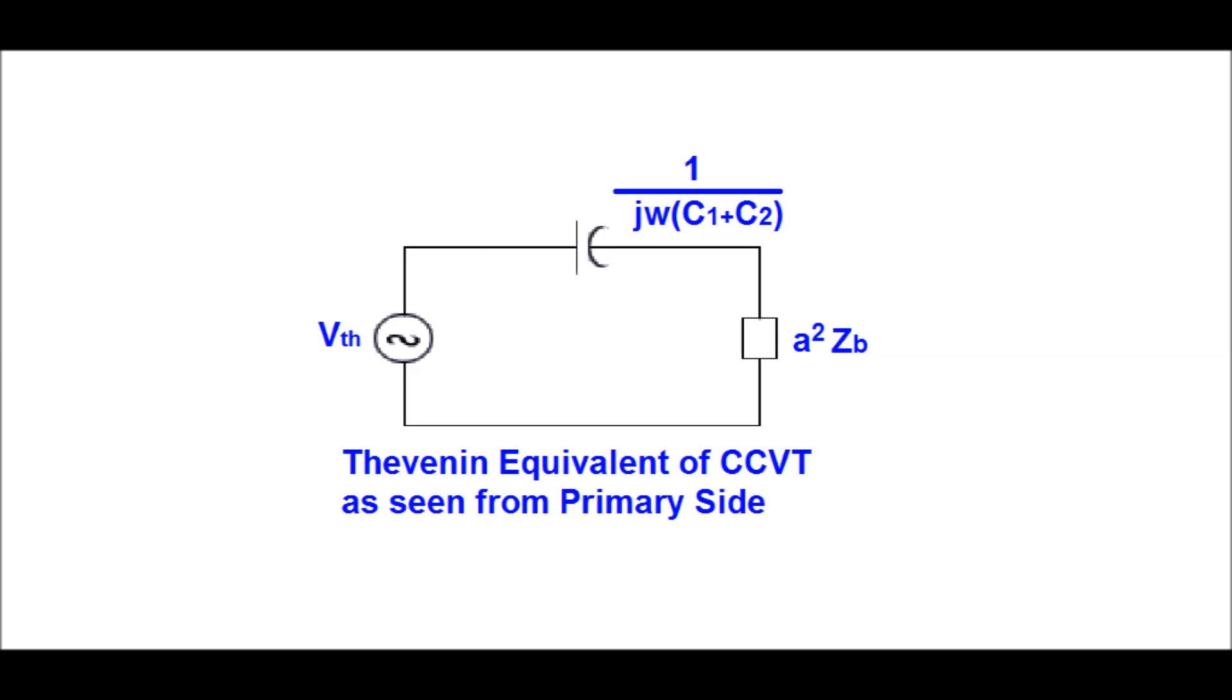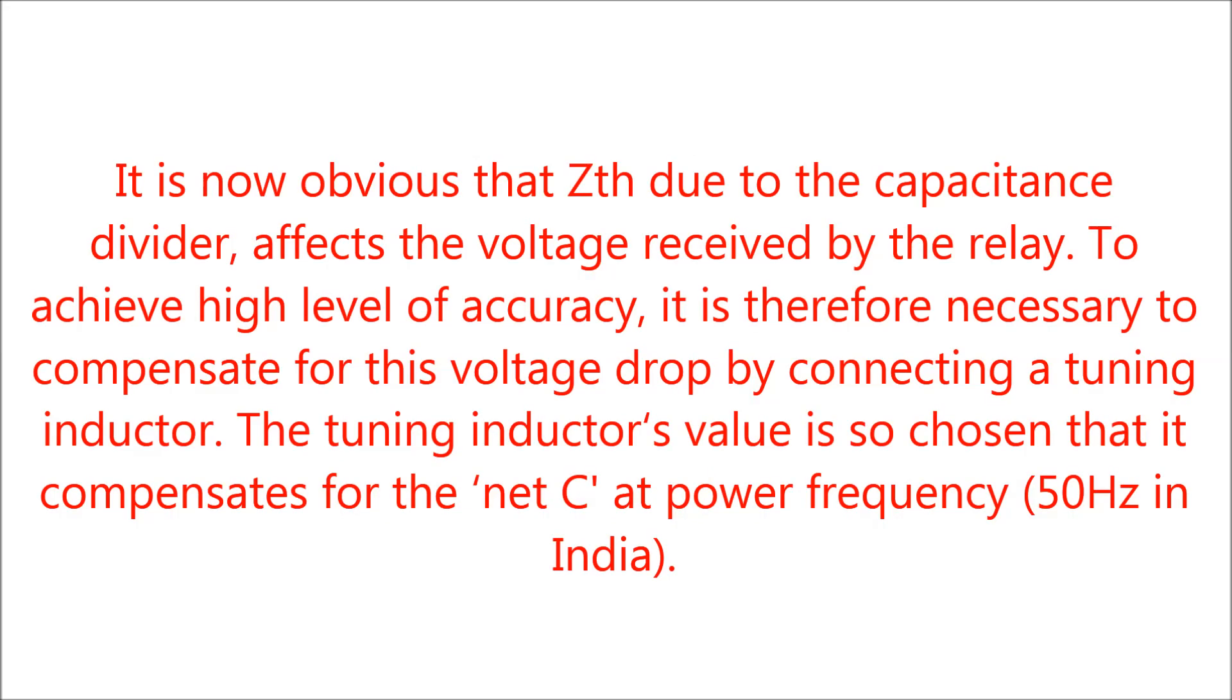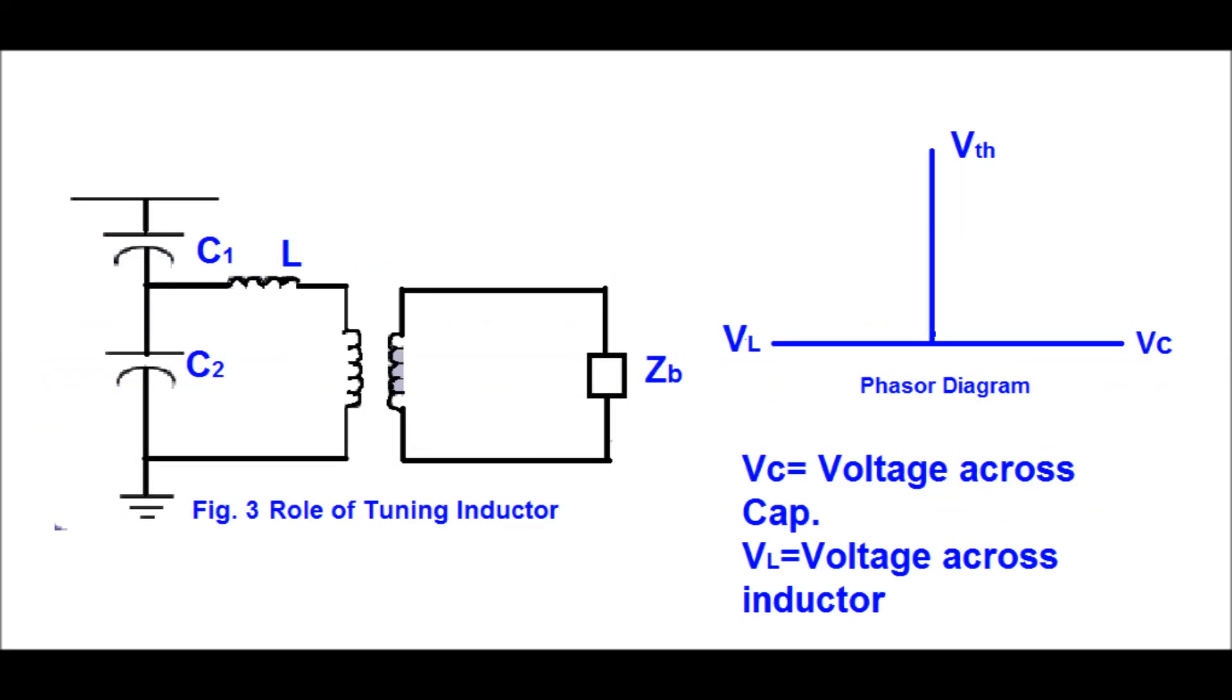Here VTH is the Thevenin's equivalent voltage, and 1/(jω(C1+C2)) is the equivalent capacitance. a²Zb is the burden referred to the primary side. To nullify the voltage drop across the capacitance, a tuning inductor L has been introduced in the equivalent circuit to compensate for the voltage drop across VC.